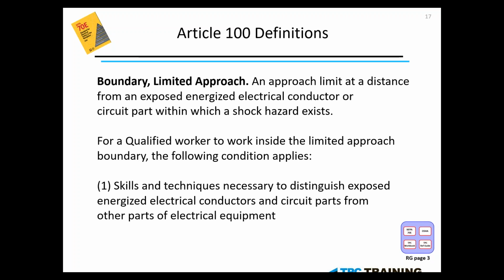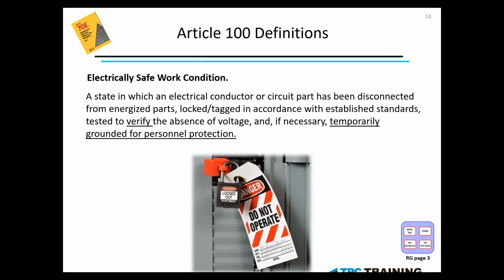The skills and techniques necessary to distinguish exposed energized electrical conductors and circuit parts from other parts are one of the requirements of a qualified worker inside these boundaries. The term electrical safe work condition is the NFPA's way of identifying with a de-energized state. It is a state in which the electrical conductor or circuit part has been disconnected from energized parts, locked out and tagged out in accordance with standards or policies, tested to verify the absence of voltage or the presence, and if necessary, utilize your temporary grounding systems. So when identifying with our most important thought process here, which is de-energizing, we need to follow these steps right here.